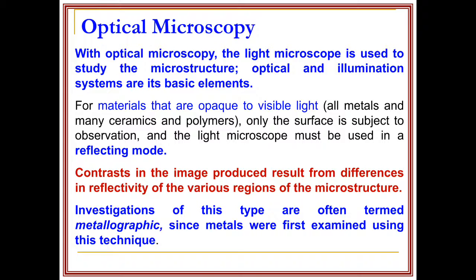Optical and illumination systems are its basic elements. This is a major difference compared to the biological microscope. For materials that are opaque to visible light — all metals and many ceramics and polymers — only the surface is subjected to observation, and the light microscope must be used in the reflecting mode. Contrast in the image results from differences in the reflectivity of various regions of the microstructure depending on your etching.